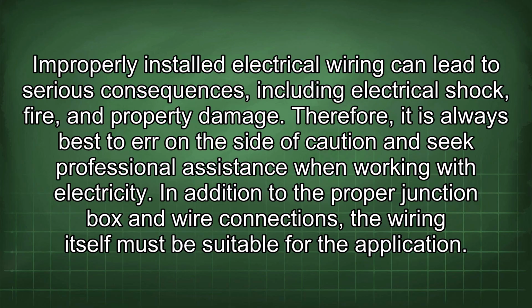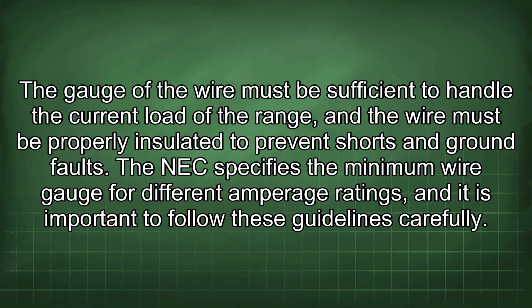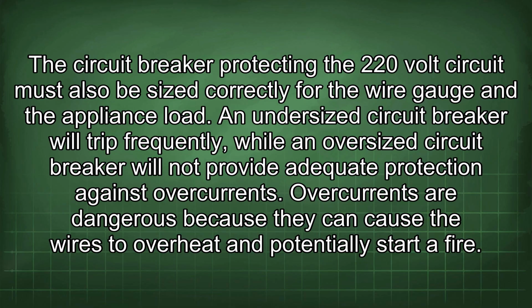In addition to the proper junction box and wire connections, the wiring itself must be suitable for the application. The gauge of the wire must be sufficient to handle the current load of the range, and the wire must be properly insulated to prevent shorts and ground faults. The NEC specifies the minimum wire gauge for different amperage ratings, and it is important to follow these guidelines carefully. The circuit breaker protecting the 220-volt circuit must also be sized correctly for the wire gauge and the appliance load. An undersized circuit breaker will trip frequently, while an oversized circuit breaker will not provide adequate protection against overcurrents. Overcurrents are dangerous because they can cause the wires to overheat and potentially start a fire.